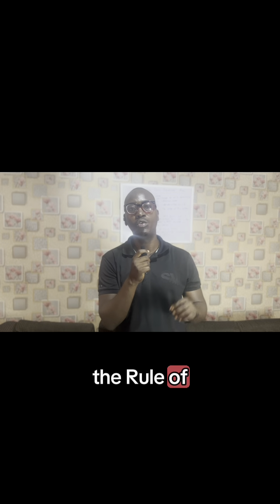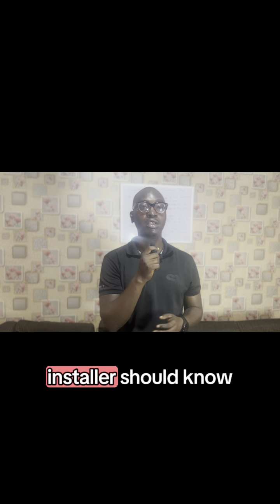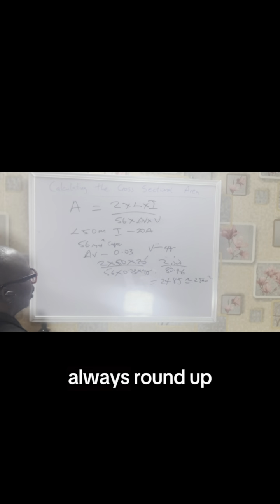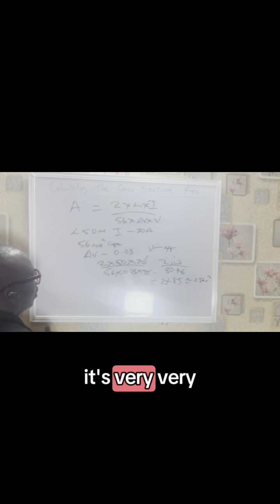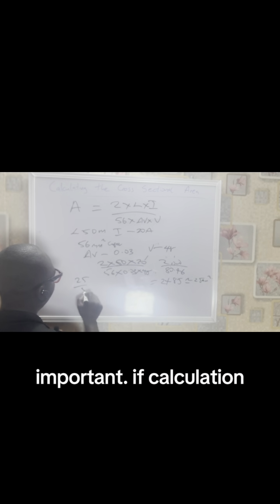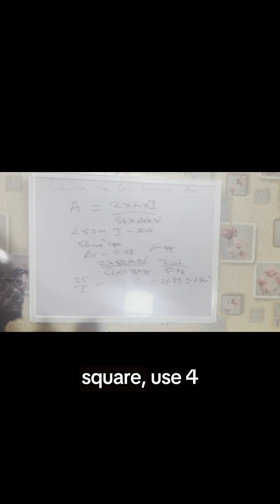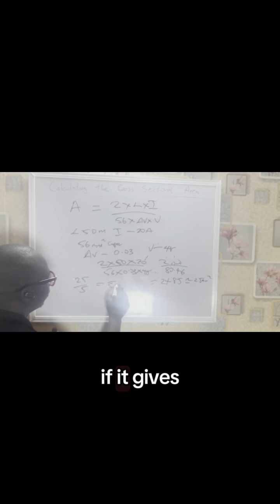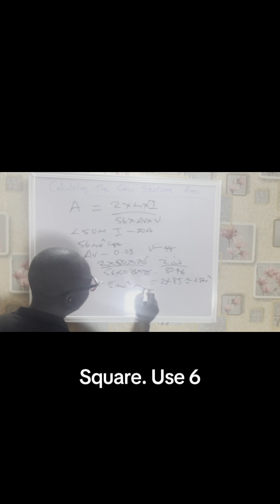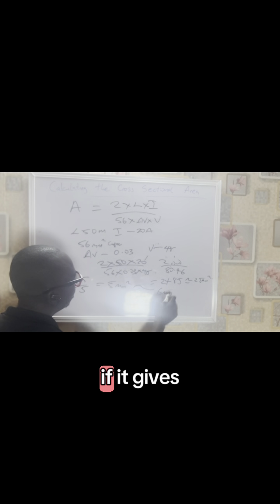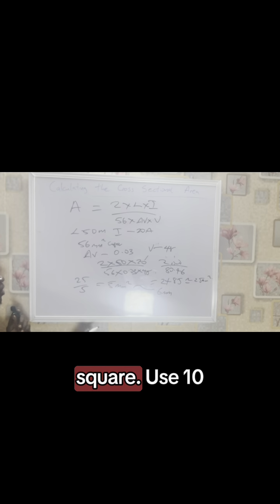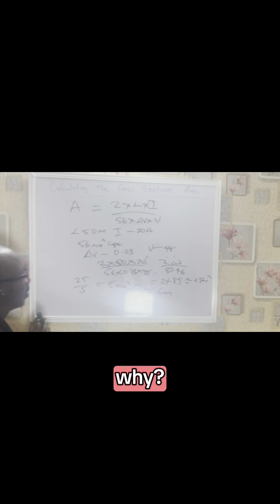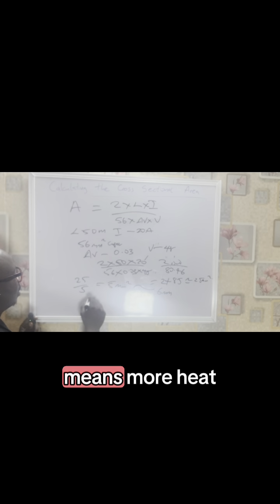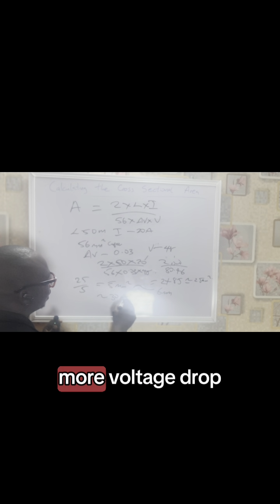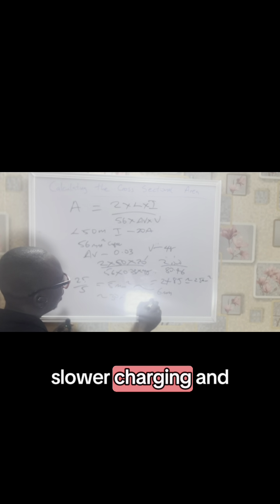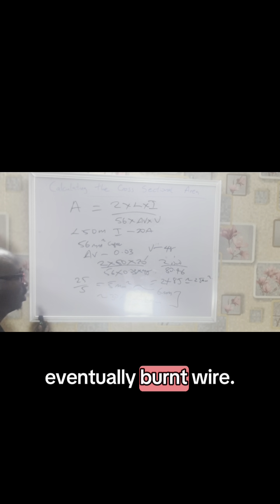So here is the rule of thumb every good installer should know. Always round up, never round down. It's very, very important. If calculation gives 2.8 mm², use 4 mm². If it gives 5.1 mm², use 6 mm². If it gives 8 mm², use 10 mm². Why? Because smaller cables mean more heat, more voltage drop, slower charging, and eventually burnt wire.